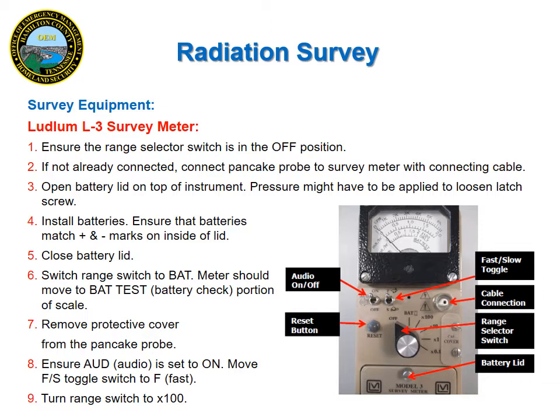In order to use a Ludlum L-3, you must first put the monitor together. This will be a lot easier to understand once we have our hands-on training, but I'm going to try to walk you through the process step by step. To begin, make sure that the range selector switch is in the off position. The range selector switch is conveniently located right under that handle. When the switch is turned off, connect the probe, pancake probe is what you're going to use, to the monitor with the connecting cable.